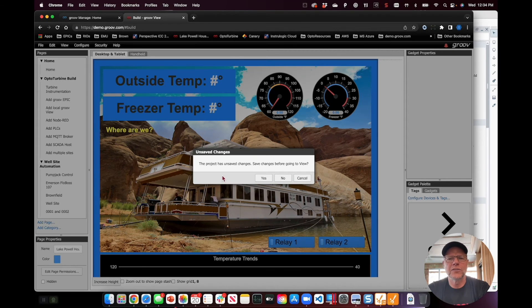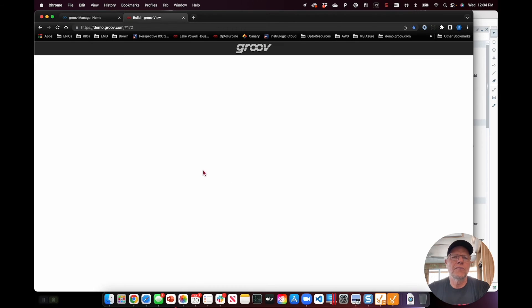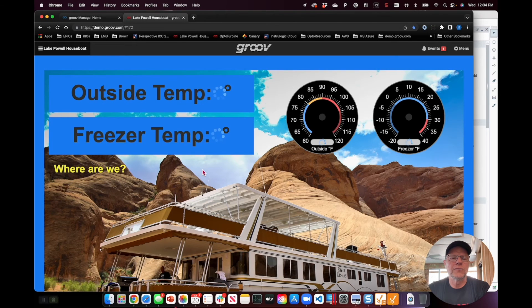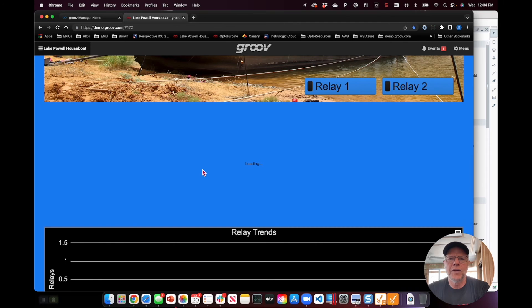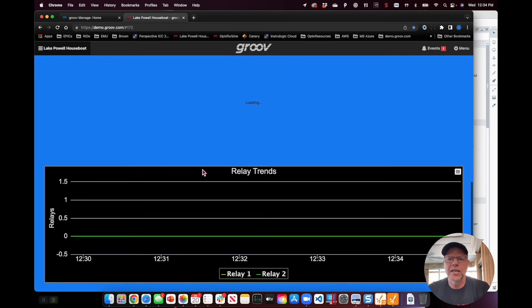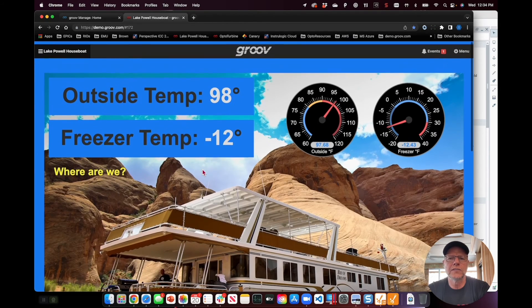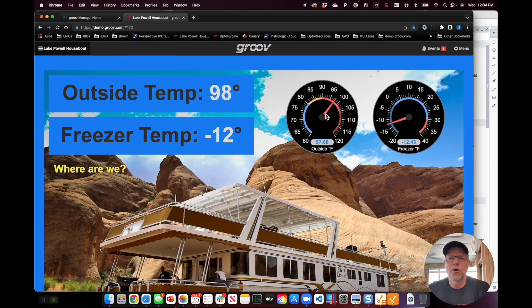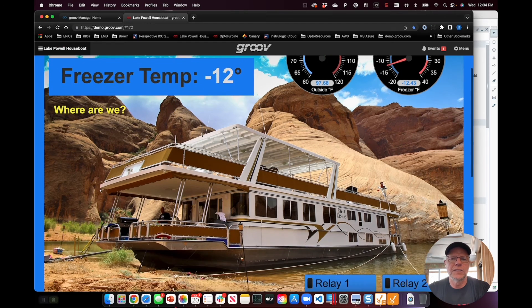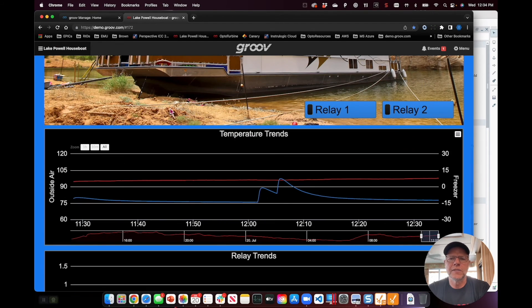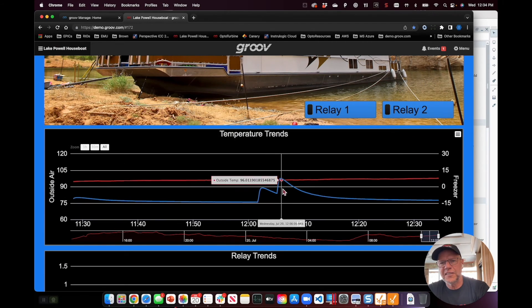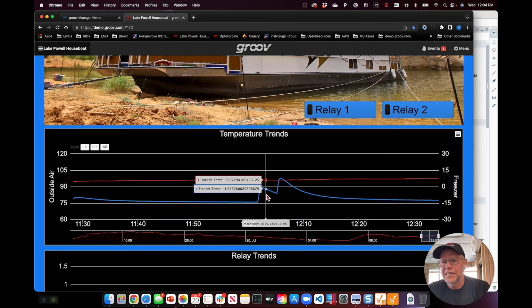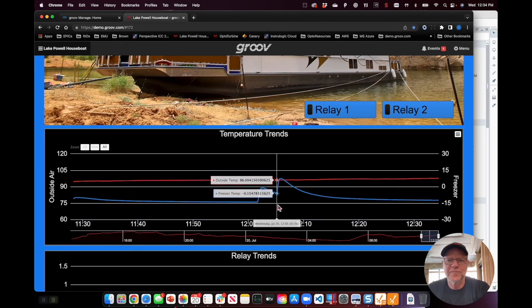So when I switch back to groov View, I'll just save changes. Now I'll switch back to groov View, here we go, and I'm loading those trends now, but all my relay trends, all my temperature trends are indeed coming through. There we go, and you can see that's that part right there in the trend is where I opened up the freezer to give you a look at that ICTD temperature probe.